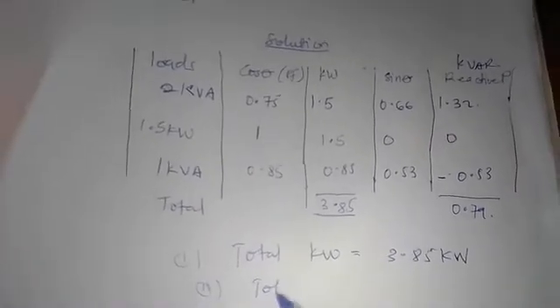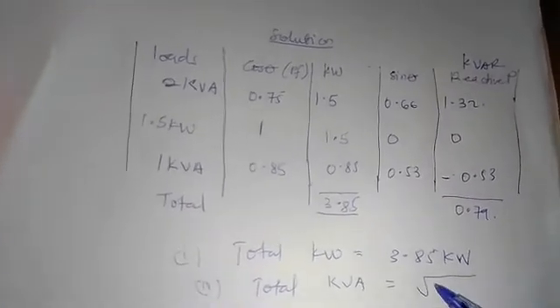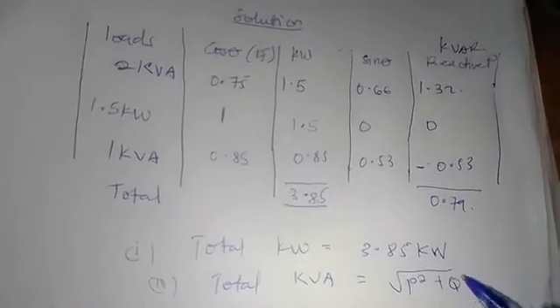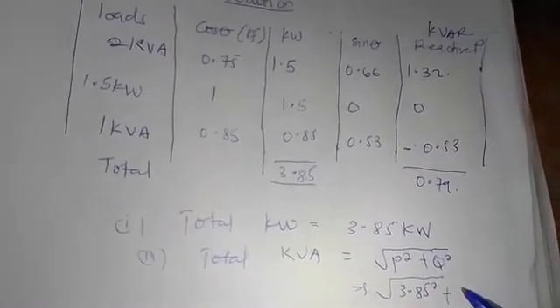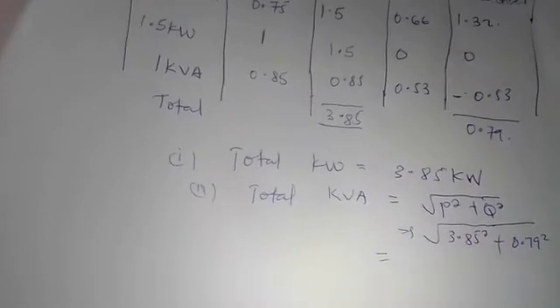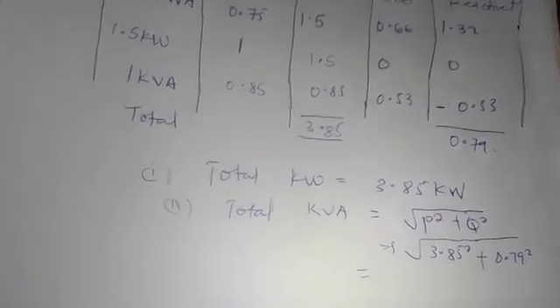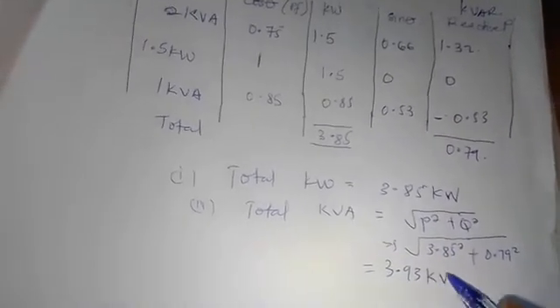For total KVA, we use the formula: KVA = √(KW² + KVAR²). That gives us √(3.85² + 0.79²) = √(14.82 + 0.62) = √15.45 ≈ 3.93 KVA. So the total KVA is 3.93 kilovolt-amperes.